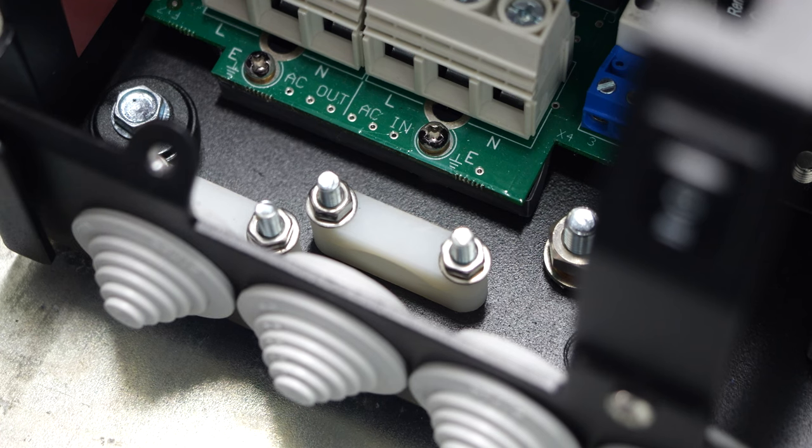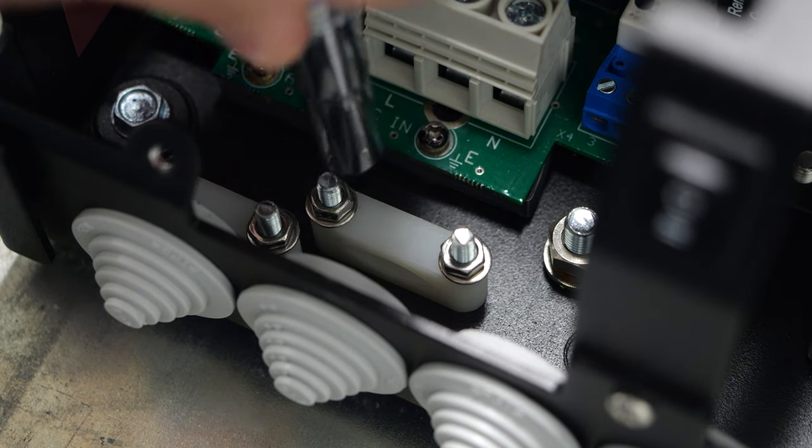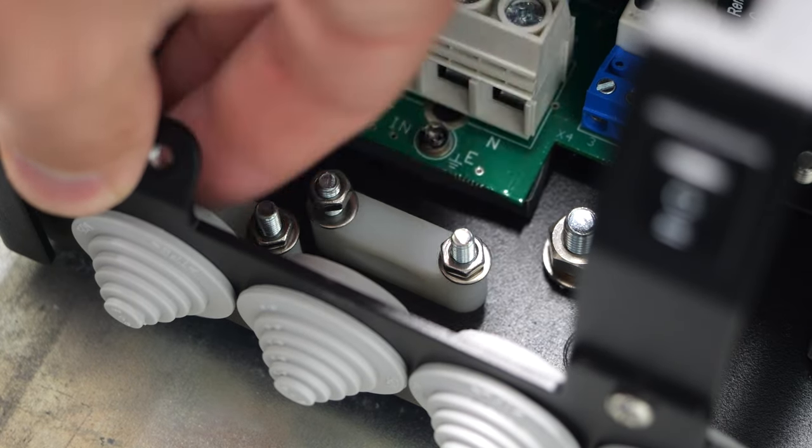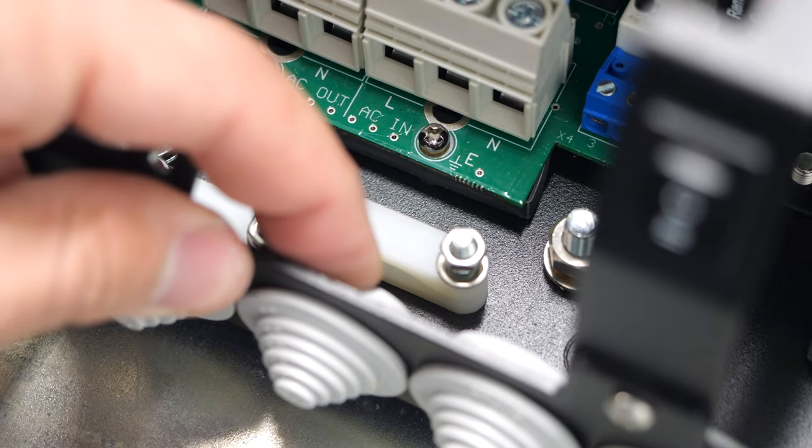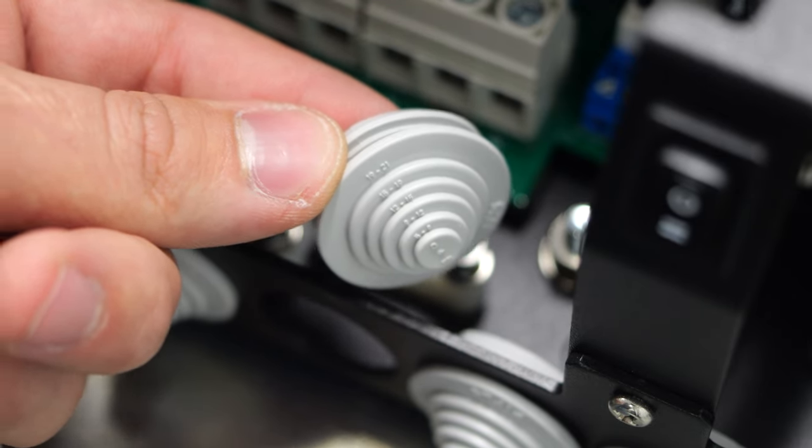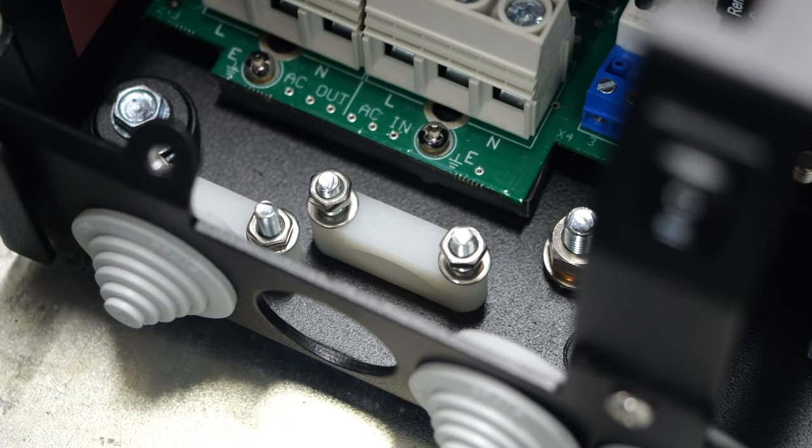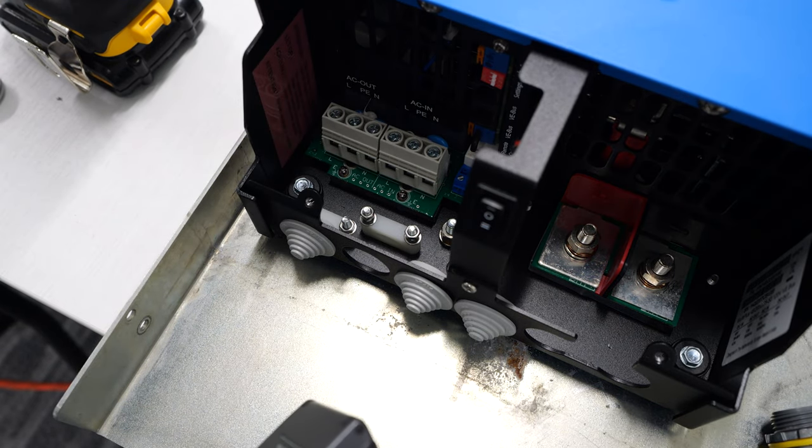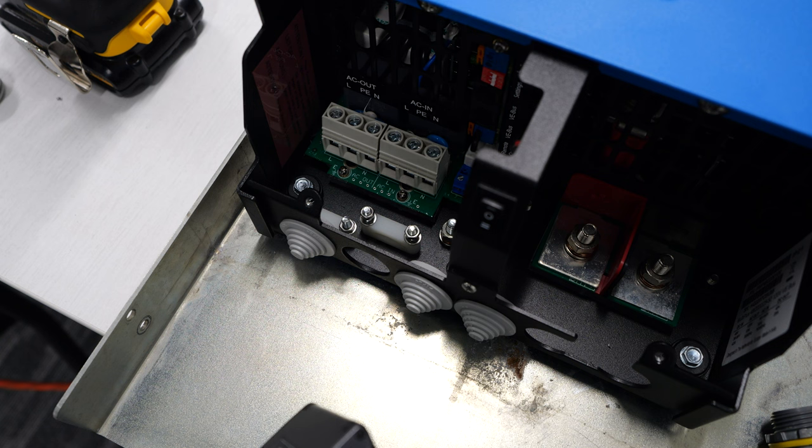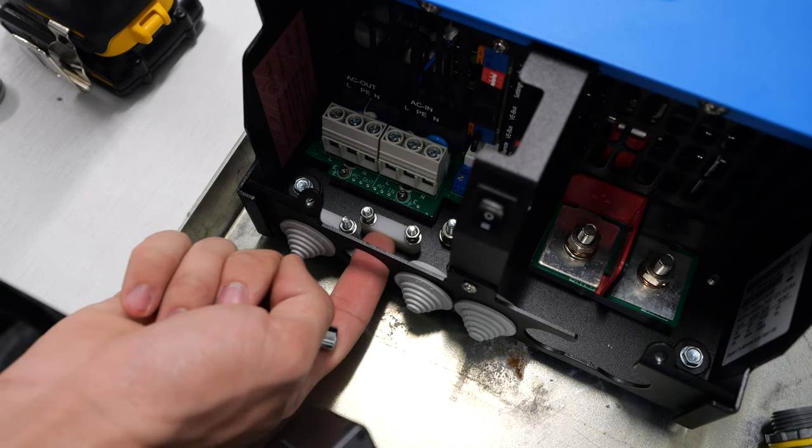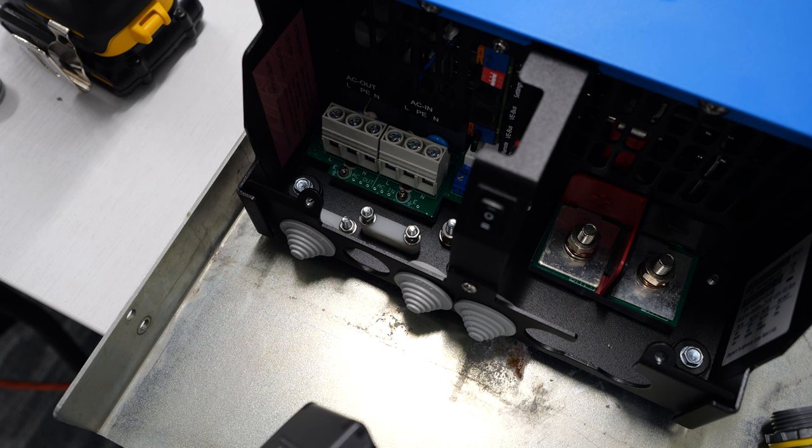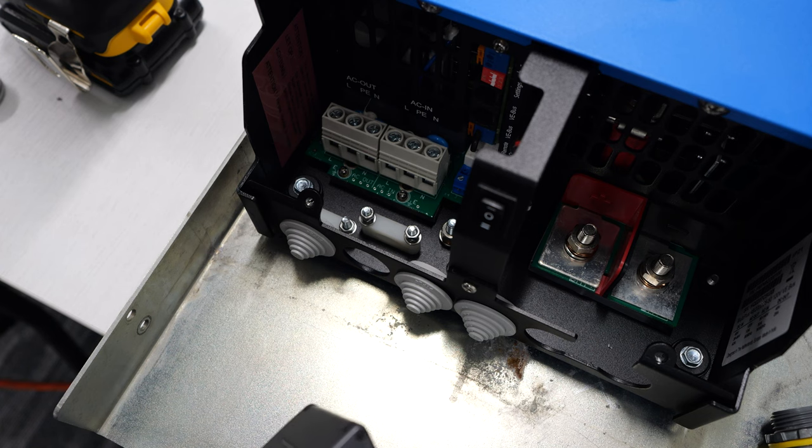In the wiring compartment, there's these little white clamps with a seven millimeter nut on them. I'm going to take those up so I can get my cable in there. There are these little boots here that theoretically you can cut to match your cable. In my case, I'm just going to omit them and just run my cord right into this clamp, get it into the terminals, and then tighten the clamp down.